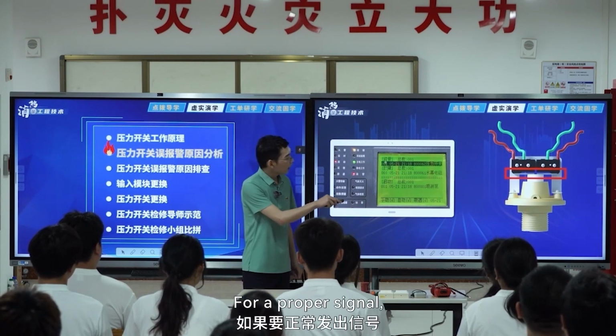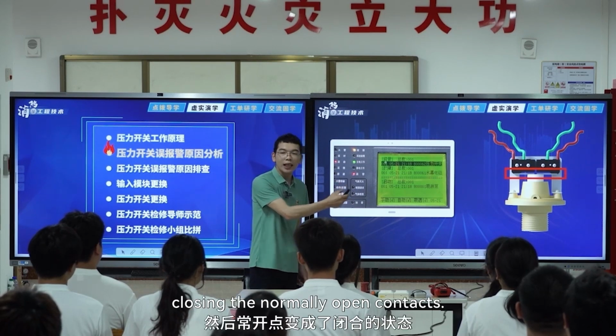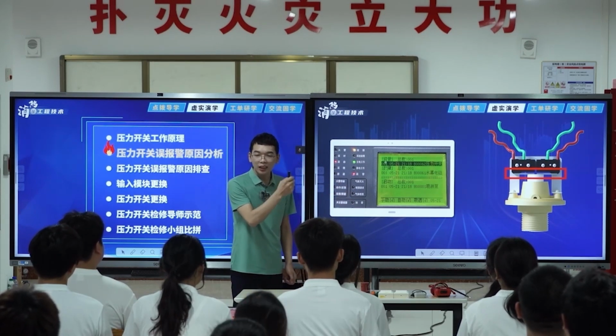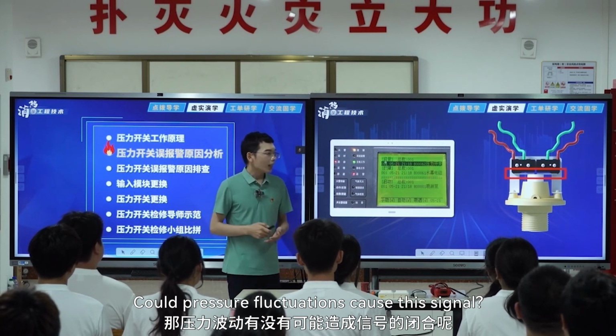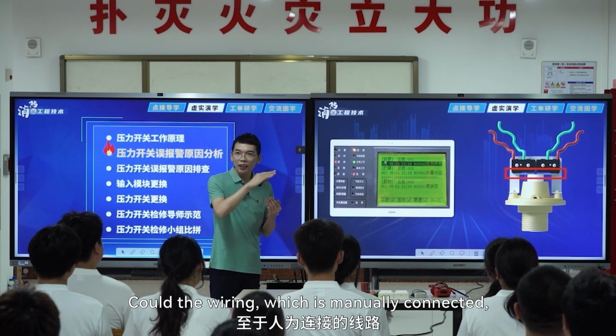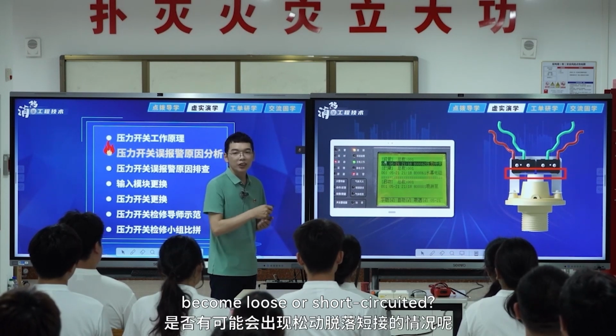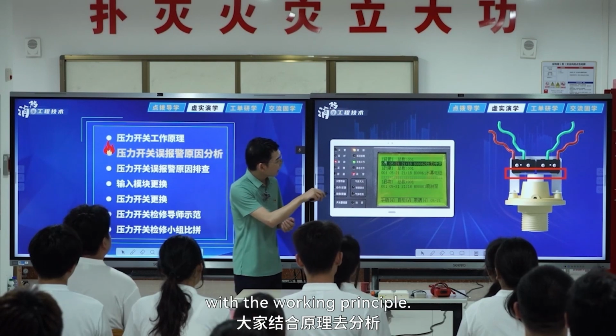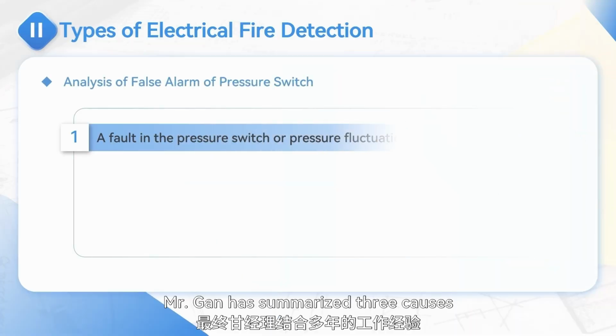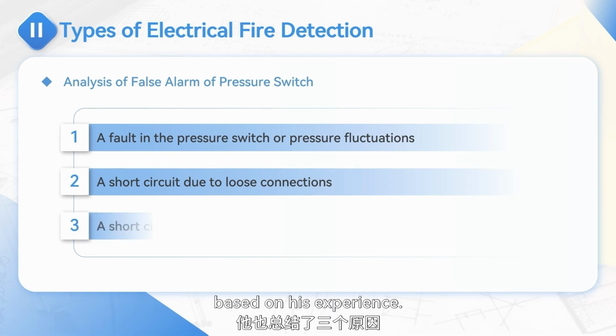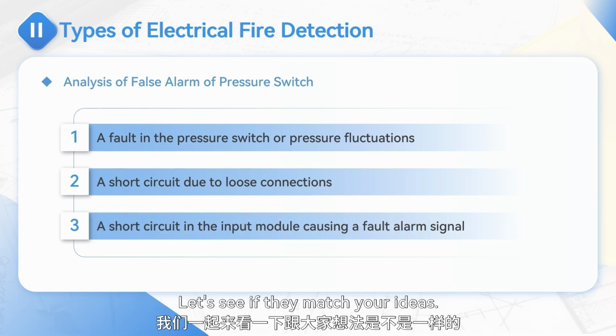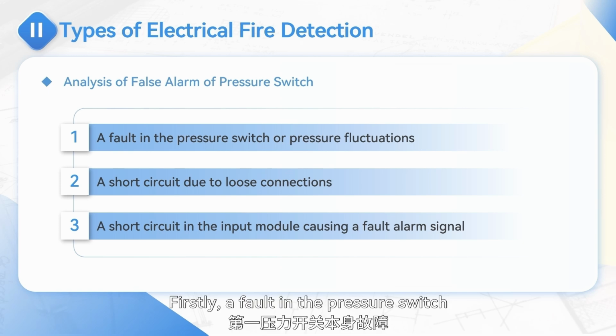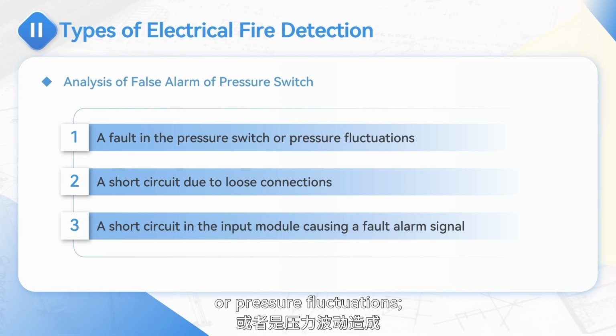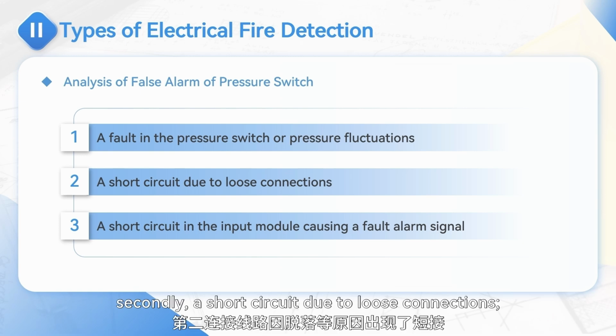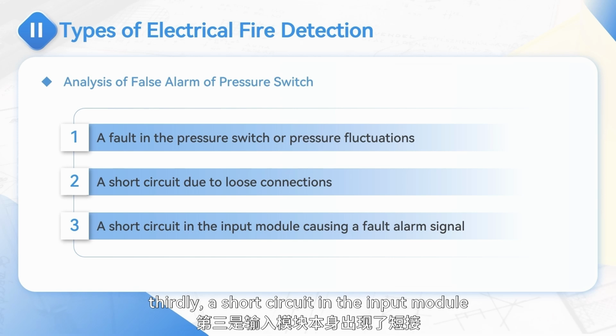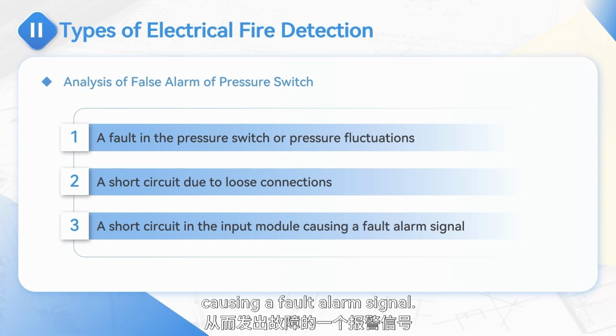For a proper signal, the movable contact must be pushed up, closing the normally open contacts. Could pressure fluctuations cause this signal? Could the wiring, which is manually connected, become loose or short-circuited? Your analysis should align with the working principle. Mr. Gon has summarized 3 causes based on his experience. Let's see if they match your ideas. Firstly, a fault in the pressure switch or pressure fluctuations. Secondly, a short circuit due to loose connections. Thirdly, a short circuit in the input module causing a fault alarm signal.